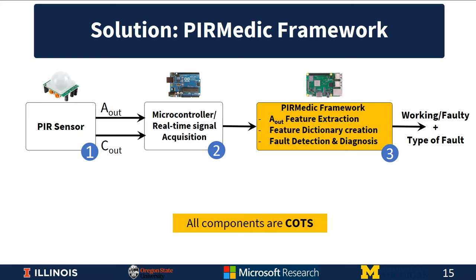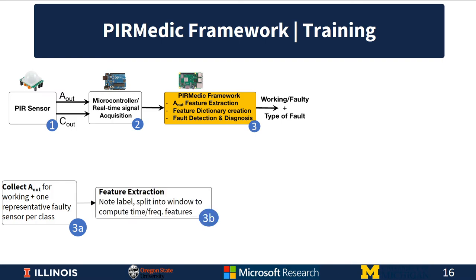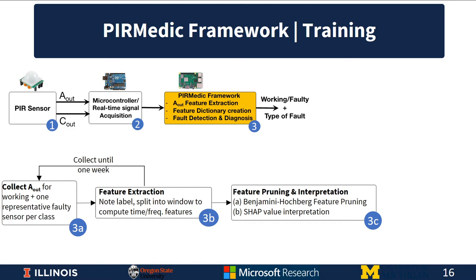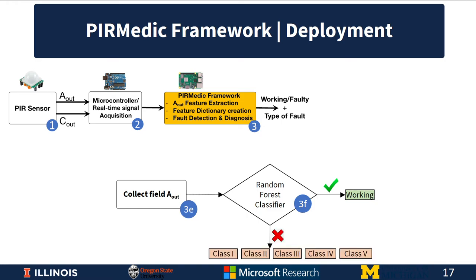In the training phase, we collect analog output for a working sensor and one faulty representative sensor per class, extract features by splitting into time windows and computing time and frequency features, repeated over a duration such as one week. We then perform feature pruning and interpretation using the Benjamini-Hochberg feature pruning and SHAP value interpretation — details in our paper — to create the feature dictionary stored on a Raspberry Pi. In deployment, we collect field analog output and send it to a random forest classifier, which determines whether the sensor is working or faulty along with the class of fault.